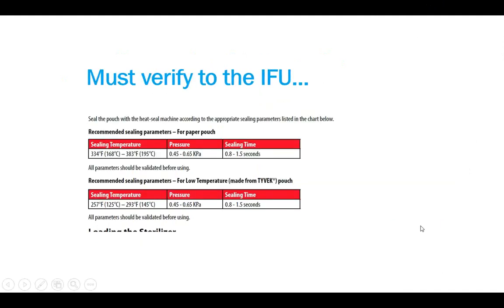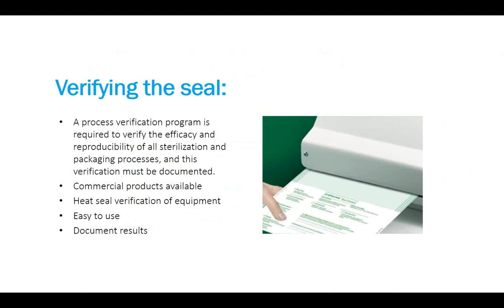This here is another IFU from another company where they tell you the pressure, the sealing temperature, and the sealing time. Remember, when we get back to the IQ, OQ, PQ, your biomed department should be making sure those parameters are being met, and that is part of a quality system. They give temperature ranges here for both low temperature and for their paper pouch, and notice they can be different between one company and the next.